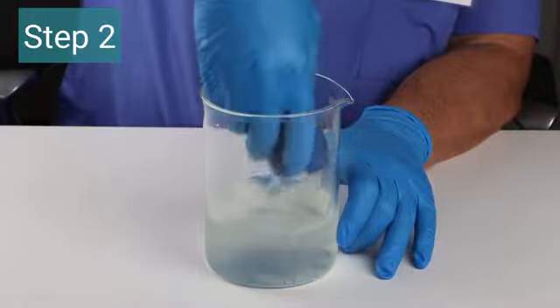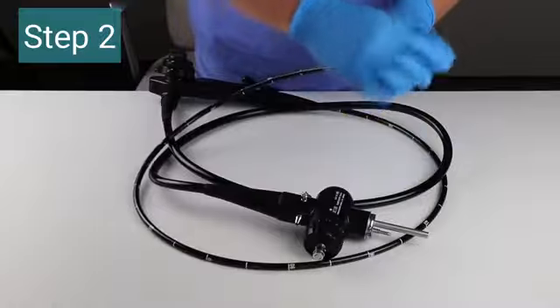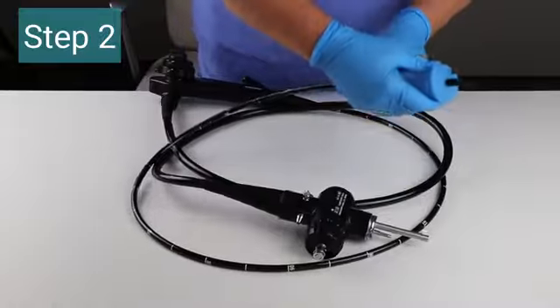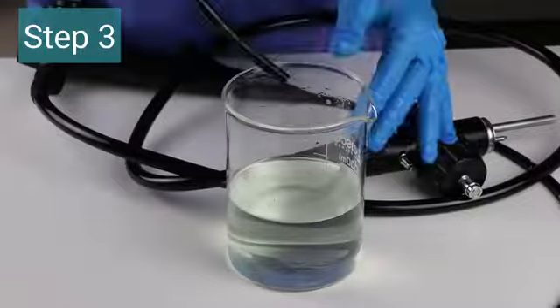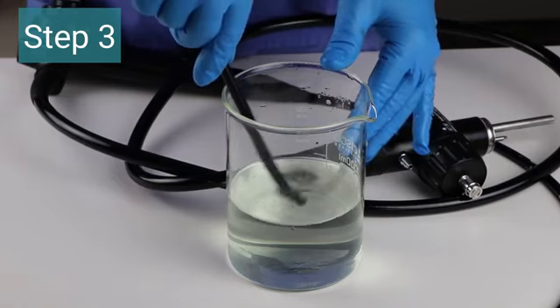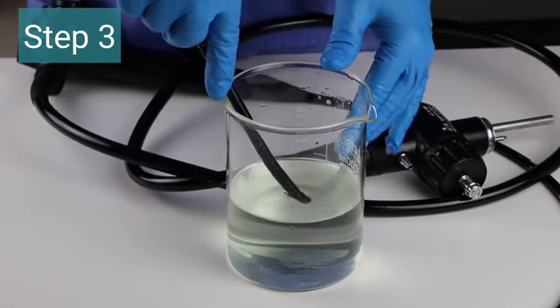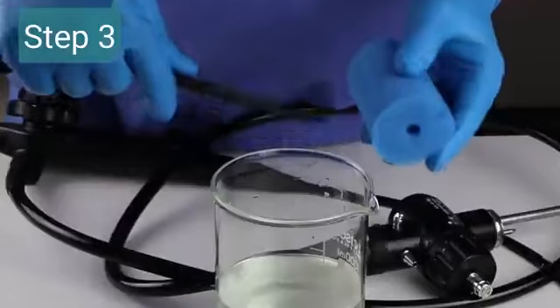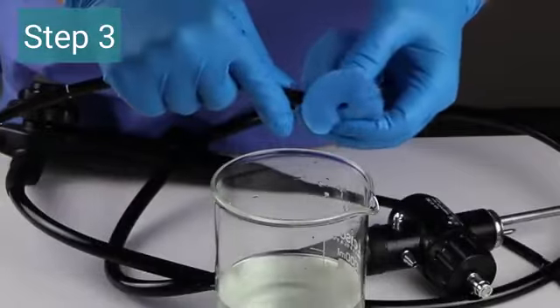Step 2. Lightly squeeze the sponge and wipe off the exterior surfaces of the endoscope. Step 3. Place the distal tip of the endoscope into the solution. Soak for 1 minute and then wipe with the sponge.